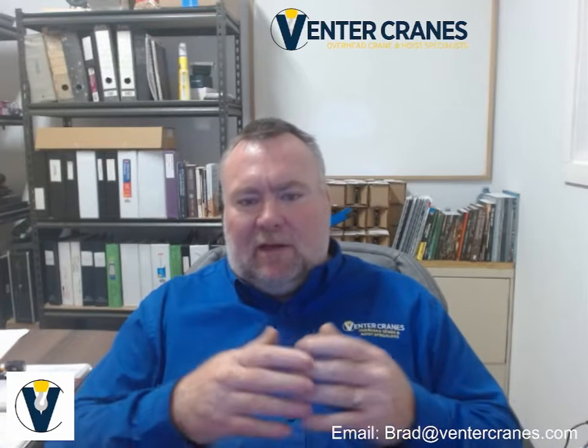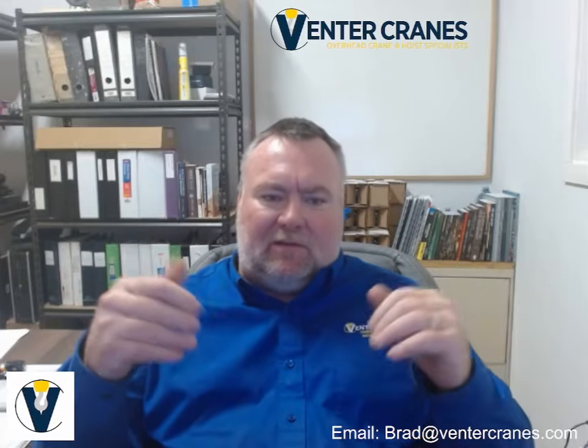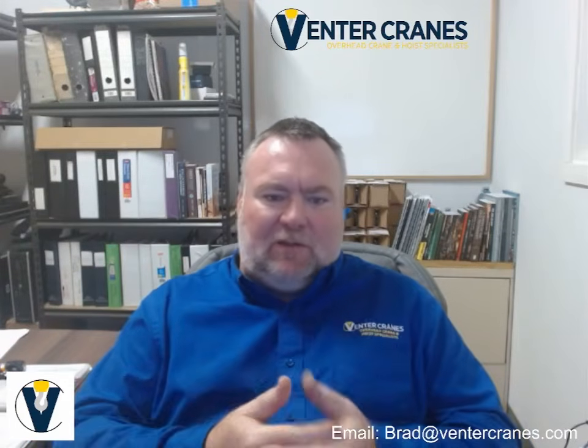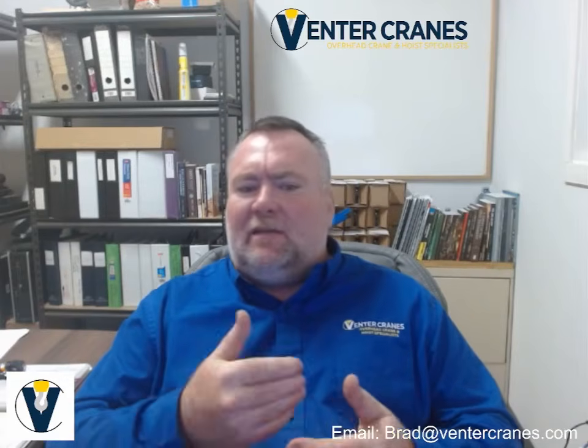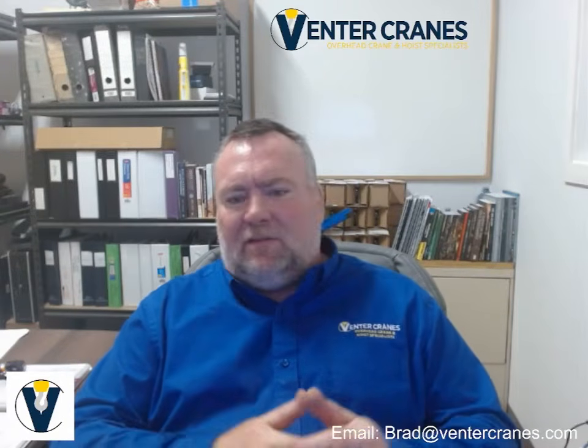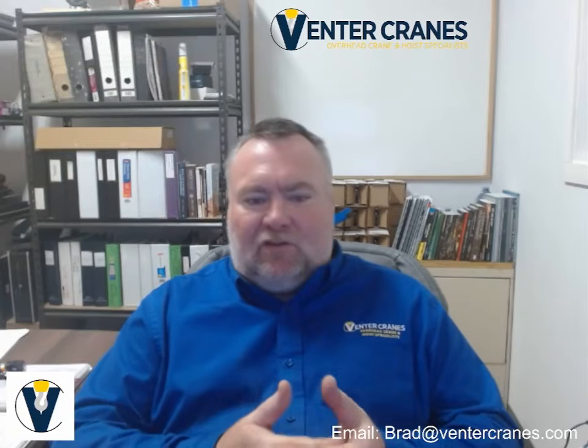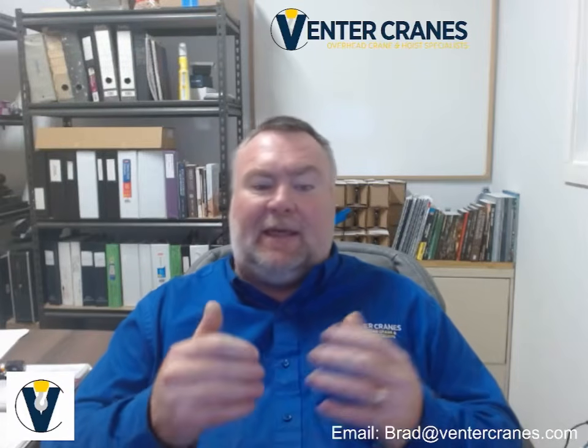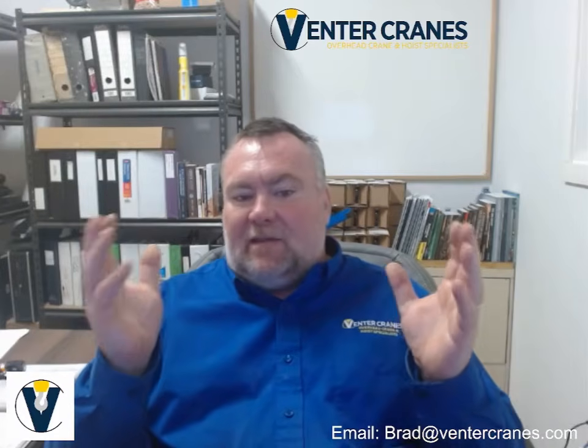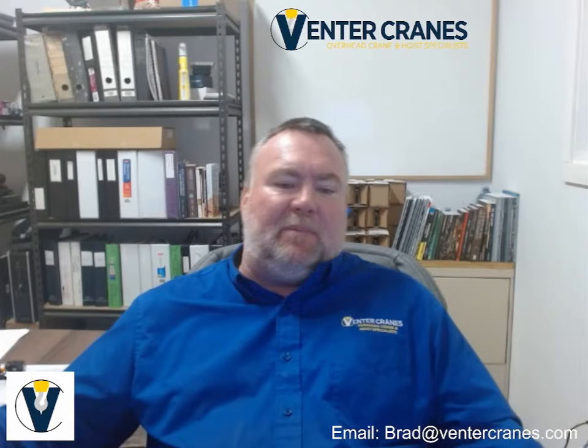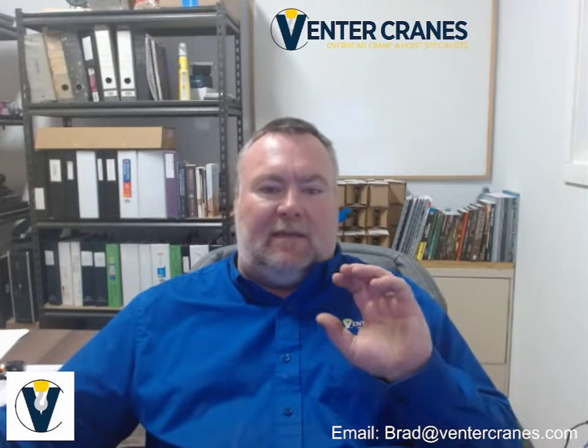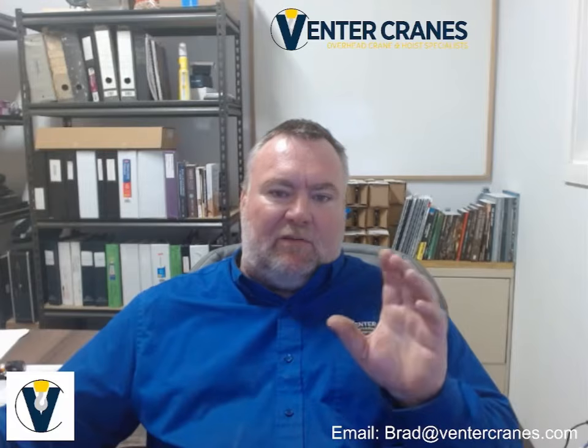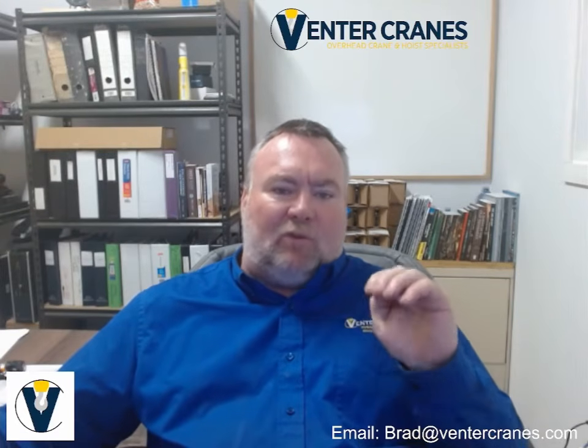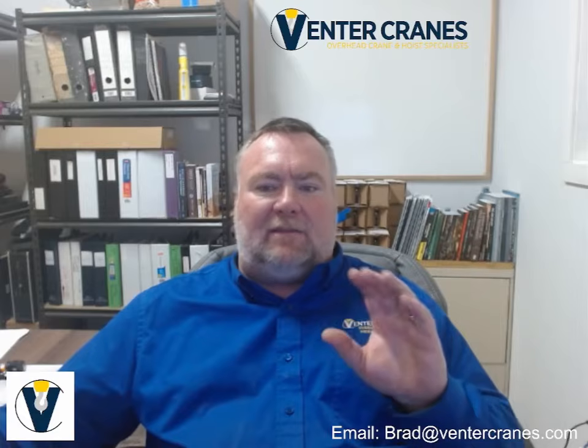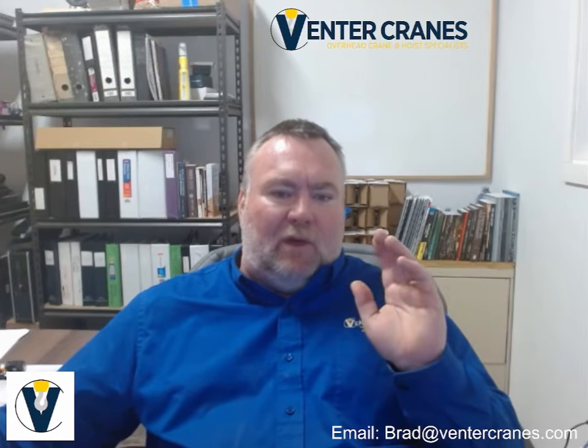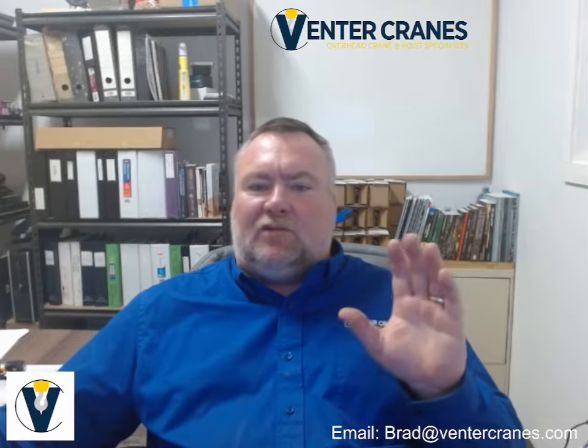So theory training content per section 9.3.2, theory-based operator training must cover OHS legislation and crane operation requirements, types of cranes and hoists, key components, safety devices and terminology, operator functional checks at start and end of shift, load handling and rigging basics, internationally recognized hand signals, operator logbooks and record keeping, facility specific policies and safety rules, manufacturer specific information for the cranes in use, right? Operators must also be trained in out of service procedures and lockout tagout to ensure they know how to respond to unsafe conditions, right?